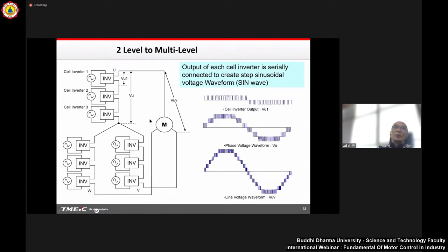So if you need more voltage, you just need to increase the number of inverter cells connected in series. For example, for 3 kV, if you want 6 kV, you need to add another 3 into the U-phase circuit. If 10 kV, you need to add another 7 cell units in series. So this is how we create a high voltage VFD from these simple inverters.